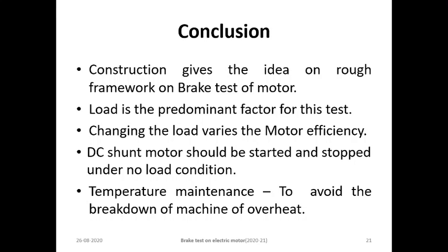And one more thing, the DC shunt motor should never be started and stopped under low load condition, because if you don't follow this rule, the motor speed will increase enormously. It means the motor speed will increase beyond the rated speed, that is 1500 rpm.